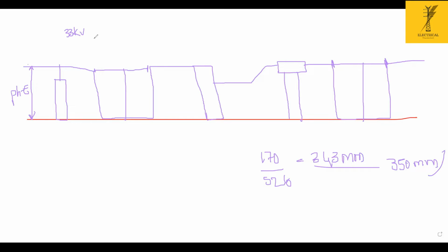Now I am talking about the sectional clearances. The sectional clearance means a person should be able to work safely on that section when the other section is in the charged condition. That is the sectional clearance.